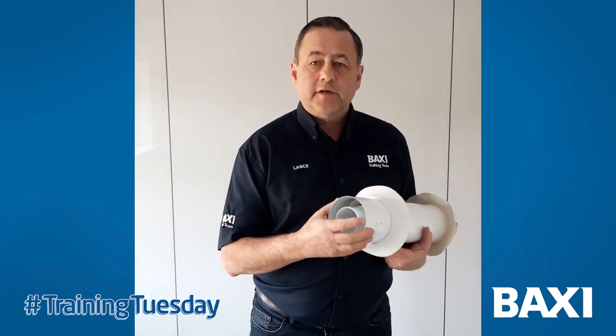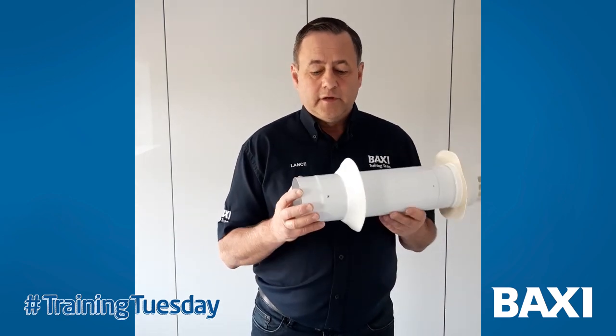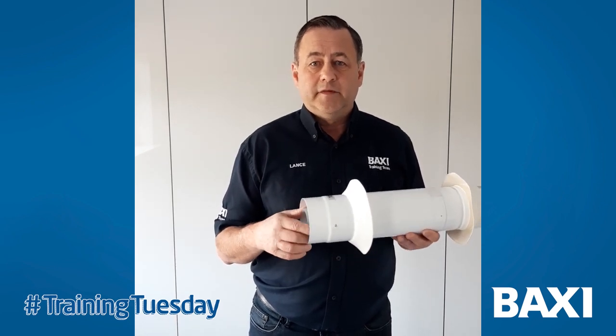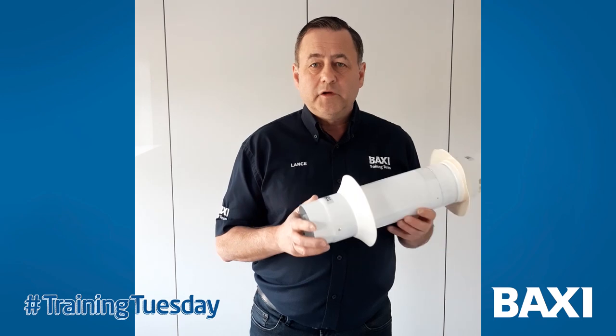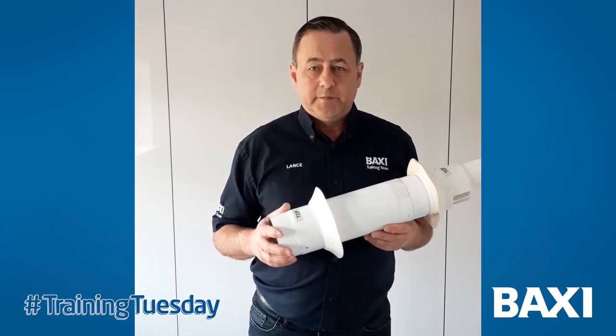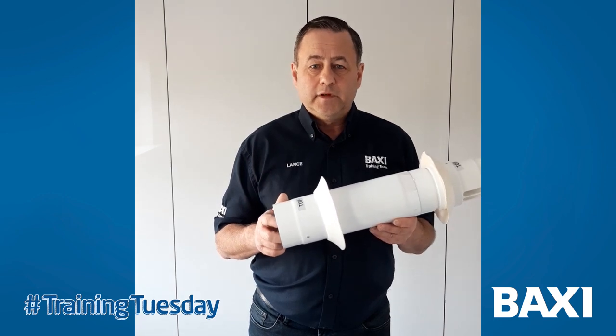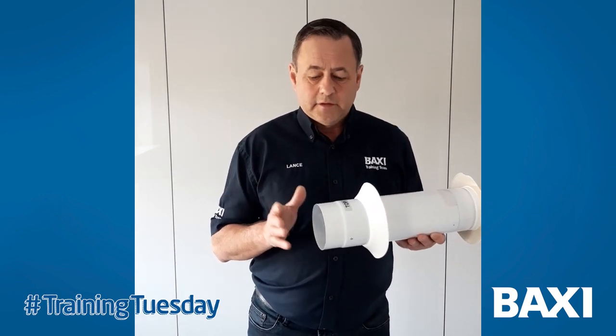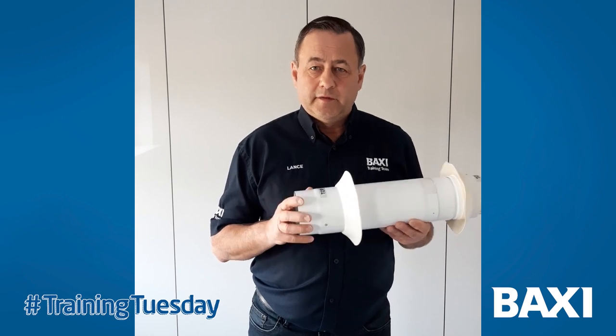This size is 60100, which is the standard size. You can run that a maximum of 10 metres flue equivalent on the combis and the system boilers. We do a larger 80125 which you can go up to a maximum of 20 metres for the combis and system boilers. The heat only is 6 metres max for the standard, and 12 metres max for the bigger flue size.